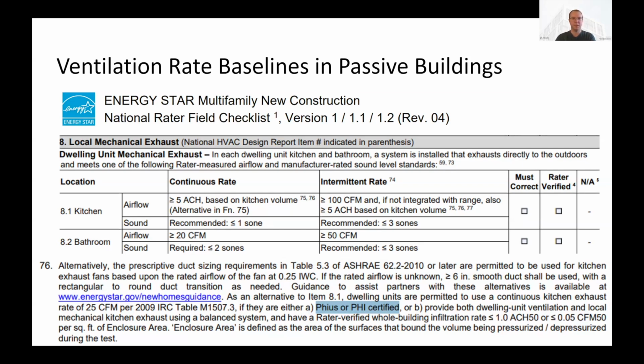Now, if we look at the footnotes that are referenced here, and I am showing footnote 76 in this document, about halfway down, it says, as an alternative to item 8.1, dwelling units are permitted to use a continuous kitchen exhaust rate of 25 CFM per this table if they are either PHIUS or PHI certified. And we can stop there. You can read the rest of it. But it's worth noting that if you're getting a PHIUS certification, you can use 25 CFM for the continuous exhaust rate in the kitchen rather than that 5 ACH. And that's generally a quite significant savings.